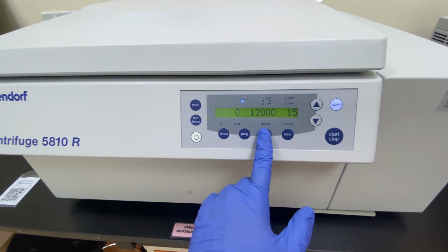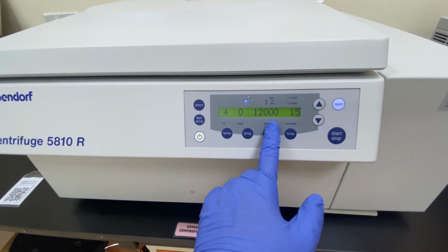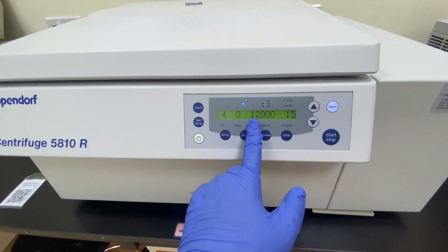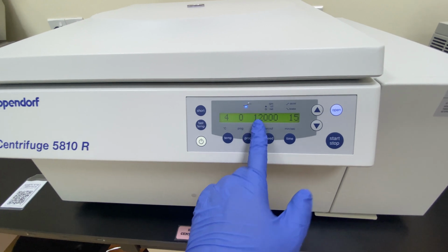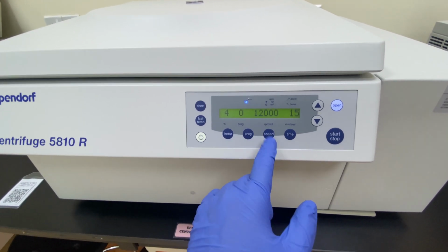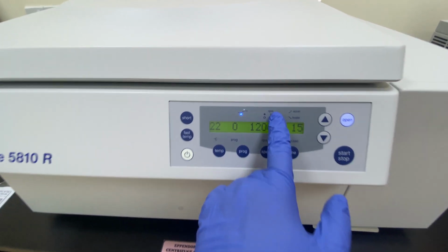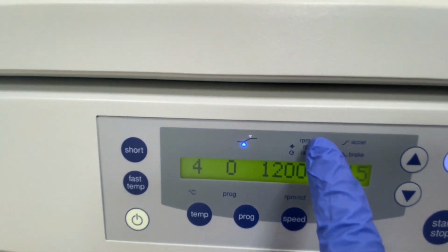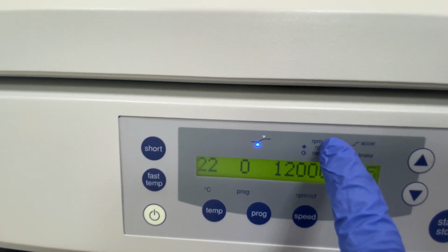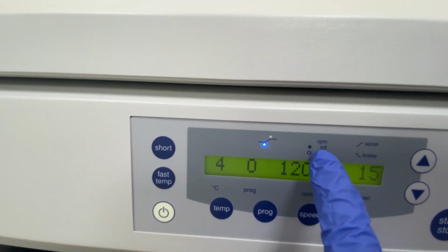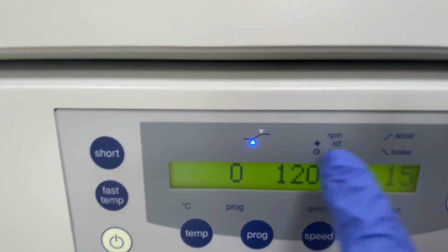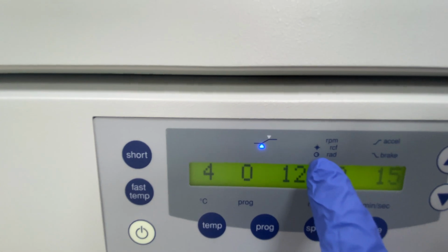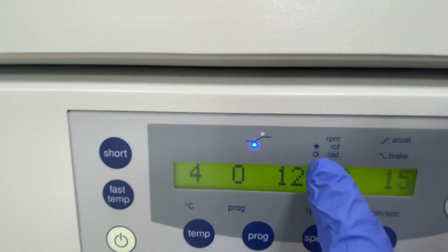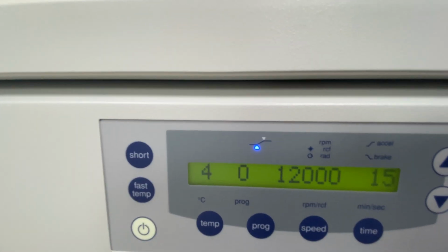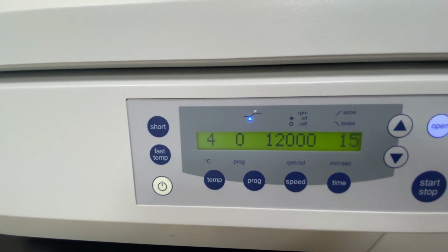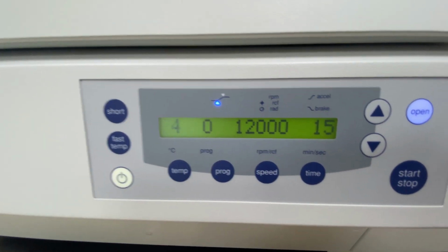This one is already set to 12,000, but you have to know whether that's RPM or RCF. There are different indicators: if there's no indicator at all, it should be RPM. If there's a star logo, it's RCF. And if there's a circle logo, it should be radial. So you have to know first which setting you want to use.